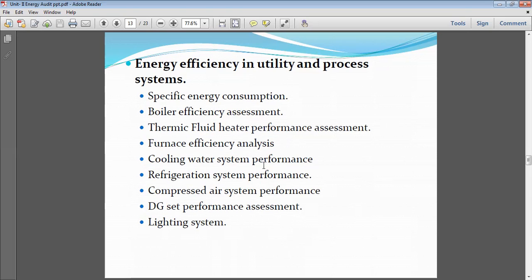Cooling water system performance: whatever cooling towers are there for the boiler or for other purposes. Refrigeration system performance: suppose it is a food industry and you are keeping the food at some -5 degrees or -10 degrees. What is the refrigeration performance? Are they performing well? What is the EER, energy efficiency ratio? What is the COP, the coefficient of performance? By calculating the coefficient of performance and the energy efficiency ratio, we can analyze the performance of the refrigeration system. If there are losses, if the coefficient of performance is very small, then we have to do some modification, or it may be some insulation failure, that is, a thermal insulation failure in the refrigeration system.